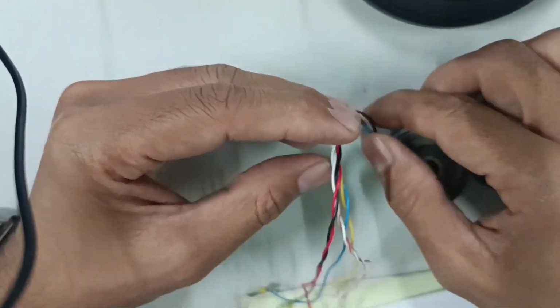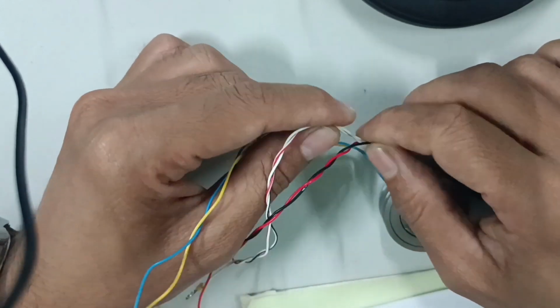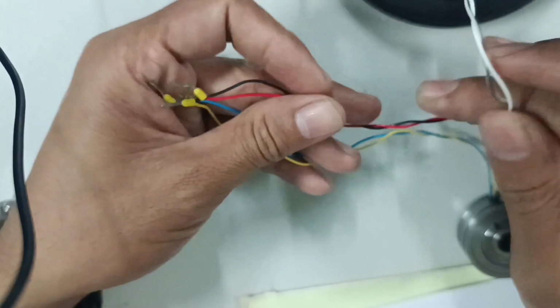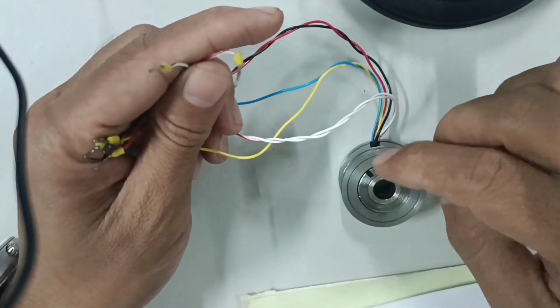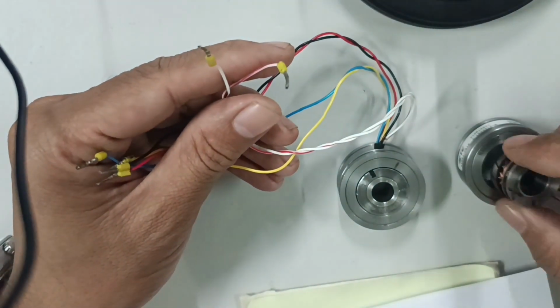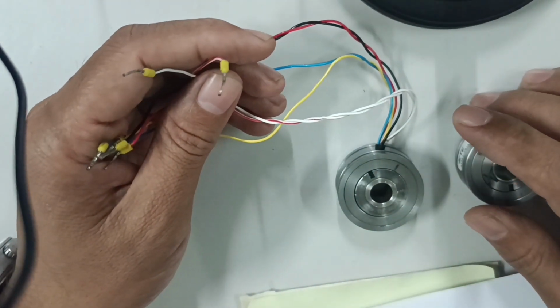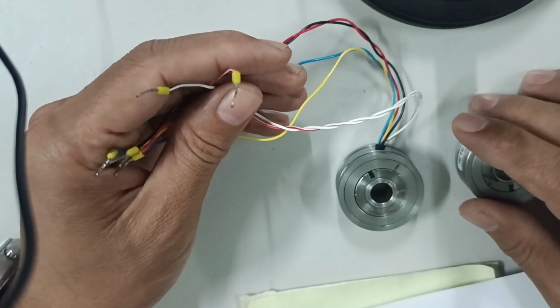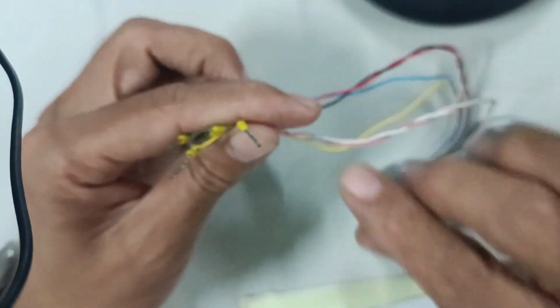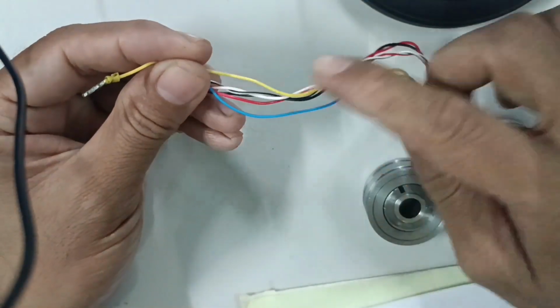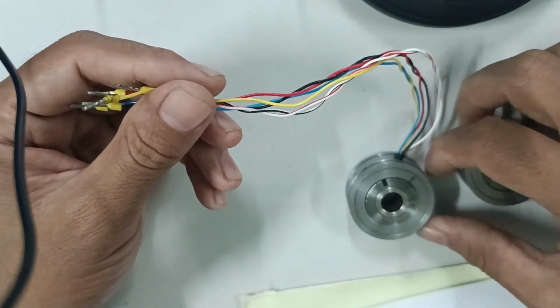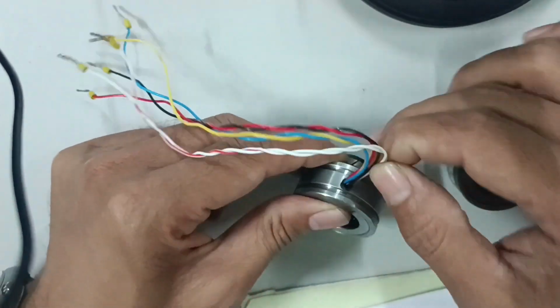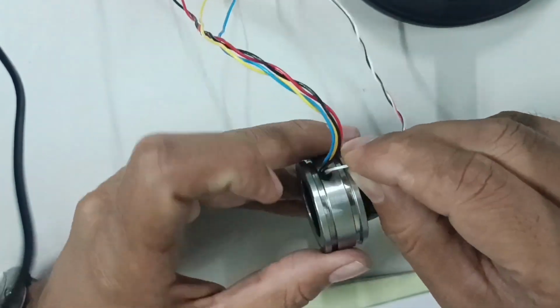Before I go into how to test the resolver, I want to share with you my own resolver problem. What actually happened in my resolver? In the first portion of my video, you saw lots of gear oil inside and outside the resolver, coming out of the resolver box. Somehow the resolver cable was scratched against other parts, so the oil and the scratch point caused a short circuit, which stopped my machine directly and showed the resolver fault.